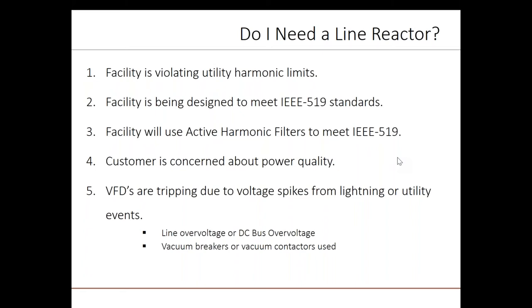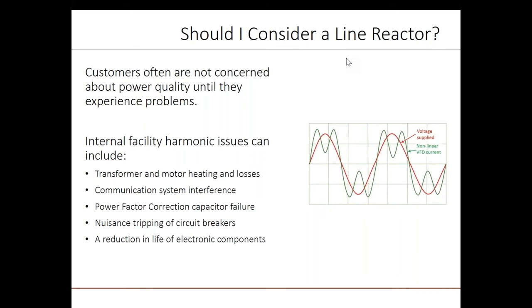Lastly, VFDs can experience tripping events, which are sometimes the result of voltage spikes from the upstream power system. This will show up as line or DC bus over-voltage faults. While line reactors are often associated with reducing current harmonics, another very important benefit is their ability to mitigate transient voltage disturbances. Vacuum breakers or vacuum contactors can cause large transient voltage spikes. Switching power factor correction capacitors can also cause voltage spikes, and so can lightning. A line reactor will help to limit voltage spikes. Customers are often not concerned about power quality until they experience problems. If any of these problems are occurring within a facility, it may indicate excessive harmonics, and line reactors should be one of the first solutions considered, especially if VFDs represent a major portion of the plant load.